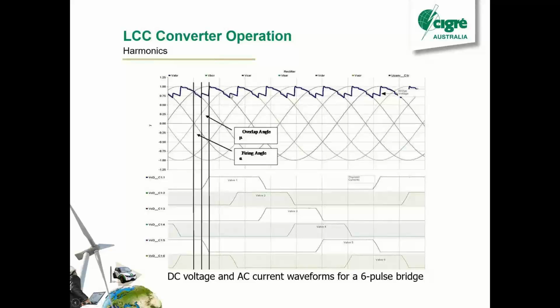Generally that's a function of your converter transformer leakage reactance, but there's a few other things you can change, but it is a desirable characteristic. You do want to have some time for that. And you can see our currents here are pretty horrible. They don't look anything like a sine wave at all, so we're going to need some serious filtering on the AC side.